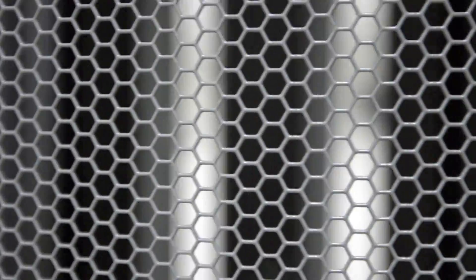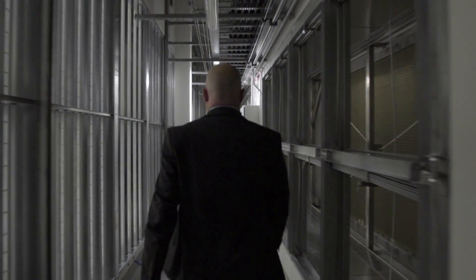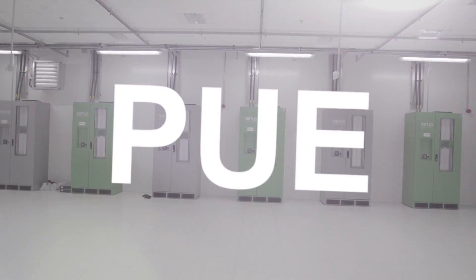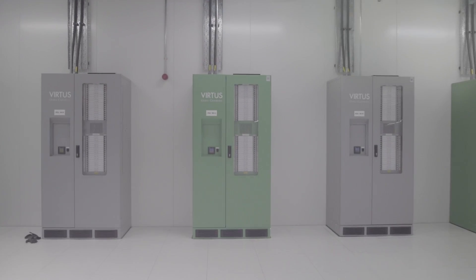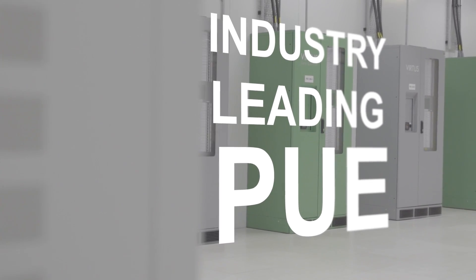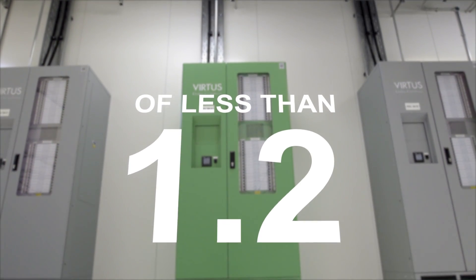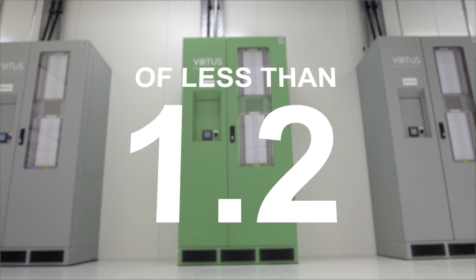The cooling technology we use here is very different and very innovative. We're the first people in London to use this method of cooling. PUE is power usage effectiveness, which is a measure used within the data centre industry. In a perfect facility the PUE would be one, and what that means is that for every unit of electricity that you consume within the IT and critical load, you're not using any other energy whatsoever to keep, for example, the building cool.